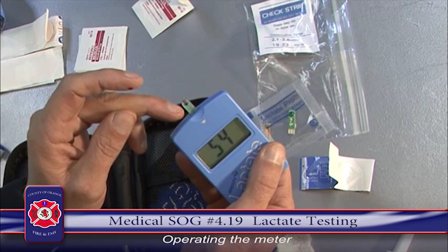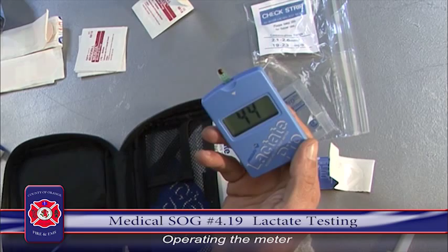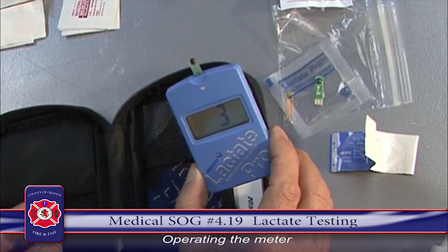It is very important that the area that you're going to test is clean. So what we suggest you do is do this, no different than you would open a needle for a syringe. Prepare it like this and hold it like this so you don't risk contaminating anything. You do the normal preparation that you would. You clean the finger. Now here's the important part. You have to remember to dry the finger off. You can't have residue and contaminants from the environment on the finger. So it's important that you dry off the finger.